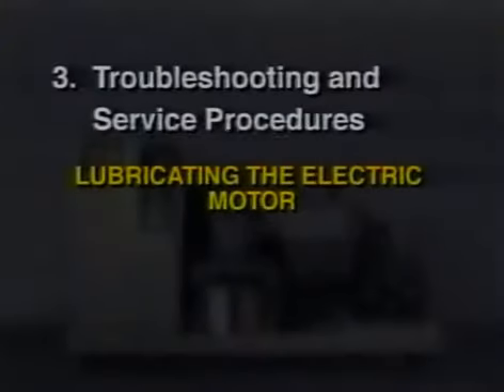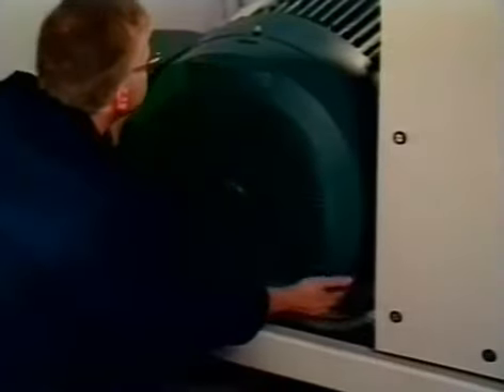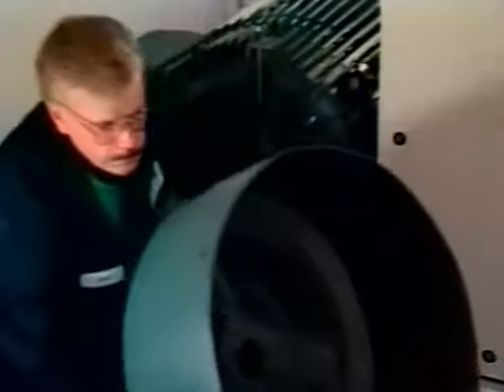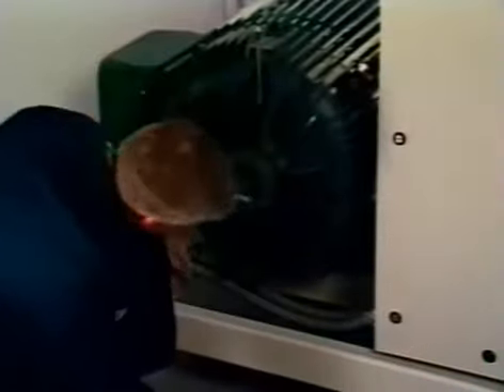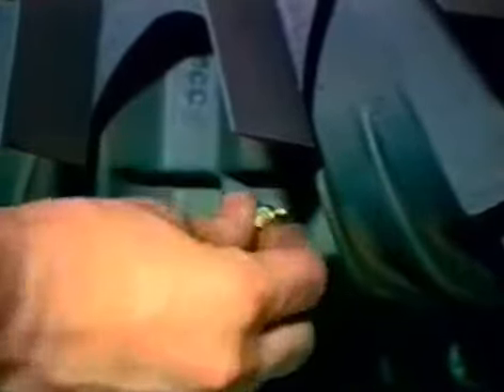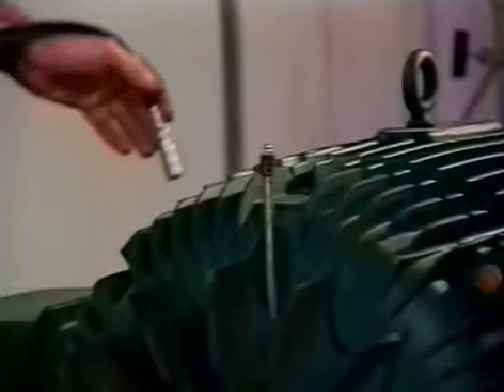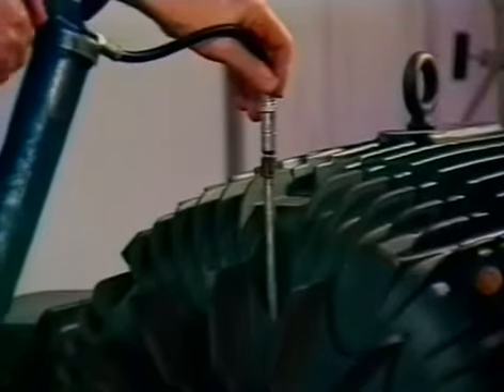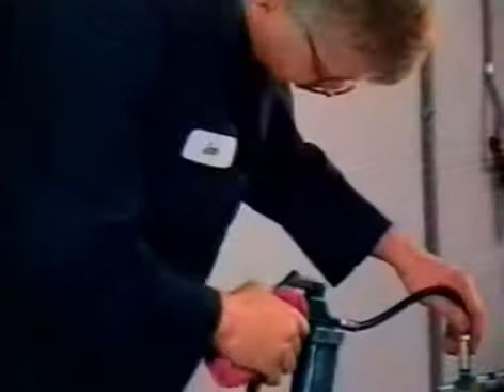Lubricating the electric motor. First, shut down the system. Then remove the grease relief plug from the front and rear bearing housing. Next, using a hand-operated grease gun, lubricate the bearing until fresh grease appears at the relief plug opening. Use only the following lithium-based lubricants, unless the motor company nameplate specifies a special lubricant.